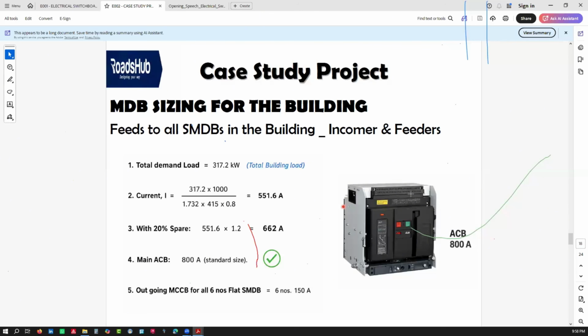So MDB sizing for the building. You've sized your SMDBs, and I've told you the SMDBs have 125. But now, if you want to design for all 7, because we have 6 floors plus common services. For common services, we had 100 in the DB that is going to supply the common services. But now, when you come to the MDB, we don't give those systems the actual value. We actually go a higher range.